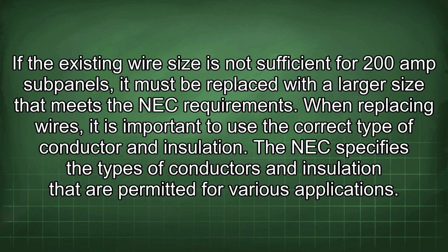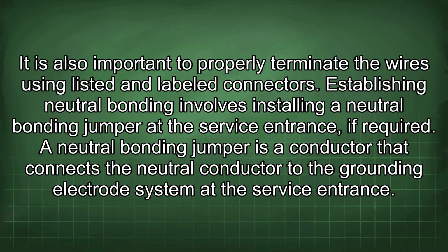When replacing wires, it is important to use the correct type of conductor and insulation. The NEC specifies the types of conductors and insulation that are permitted for various applications. It is also important to properly terminate the wires using listed and labeled connectors. Establishing neutral bonding involves installing a neutral bonding jumper at the service entrance, if required.